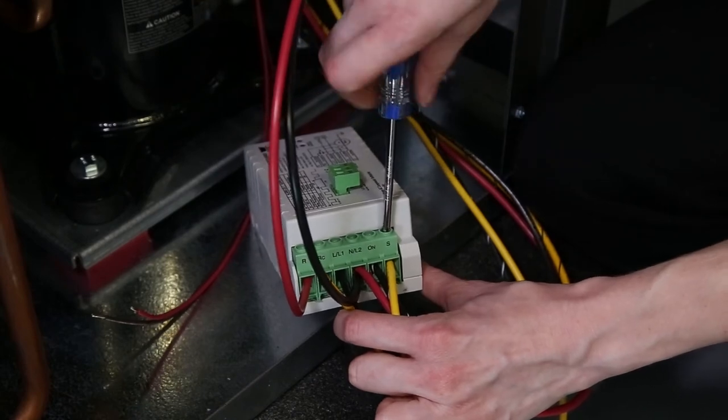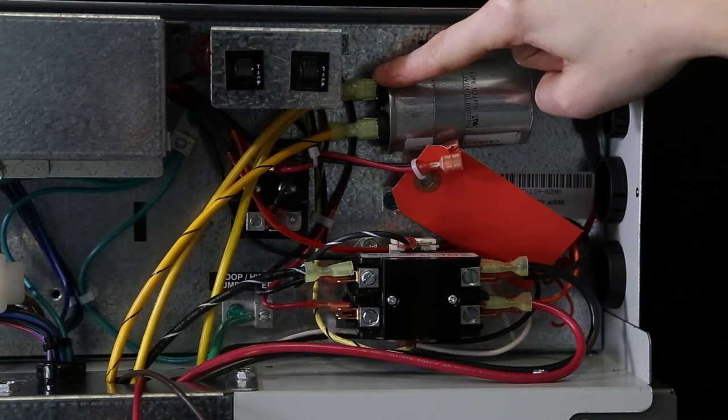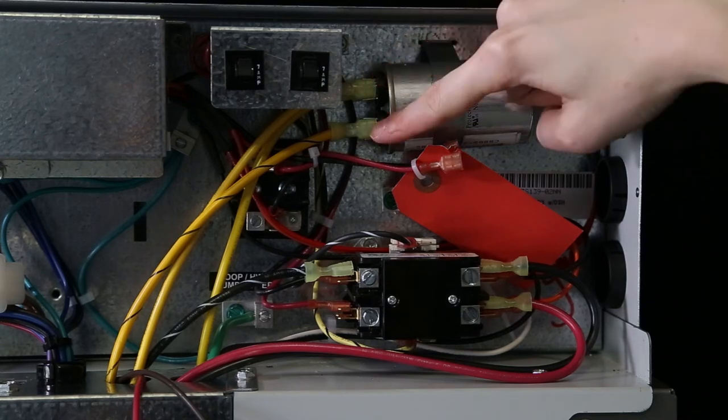The solid yellow 10 gauge wire that runs from the S terminal on the soft start module to the capacitor must go to the same side of the capacitor as the solid yellow 10 gauge start wire from the compressor. The yellow 10 gauge wire with the black stripe connects to the opposite side of the capacitor.